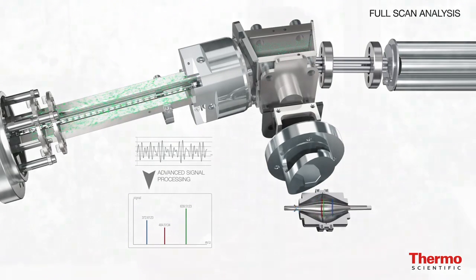On the quantitative workflow I expect it to perform exactly the same as we are used to from the triple quadrupole instruments. On the qualitative screening side, my expectation is that we will find more unexpected residues and contaminants that would normally not be looked for. Since it's so easy to look for all of those, we are likely to pick up more contaminants and residues. This data would also be of interest to retrospectively screen for compounds that may not be of interest at this moment but may become relevant in the near future.